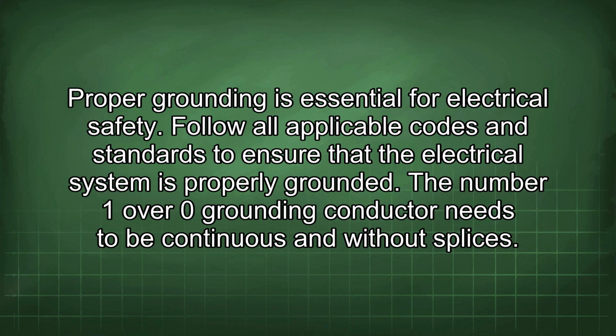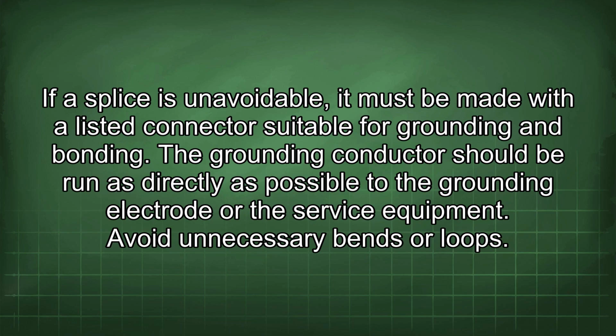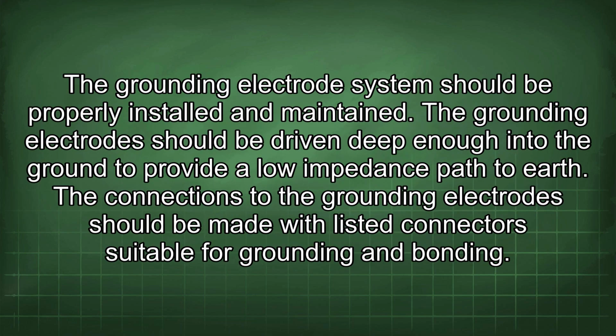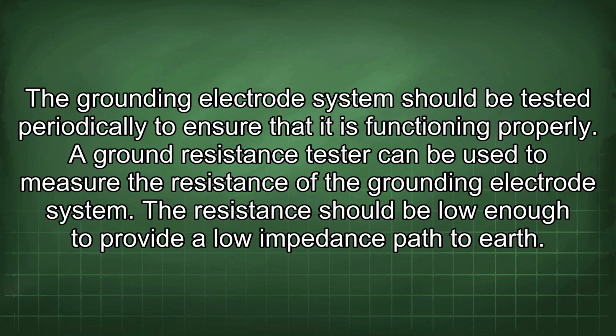The number 1/0 grounding conductor needs to be continuous and without splices. If a splice is unavoidable, it must be made with a listed connector suitable for grounding and bonding. The grounding conductor should be run as directly as possible to the grounding electrode or the service equipment. Avoid unnecessary bends or loops. The grounding electrode system should be properly installed and maintained. The grounding electrode should be driven deep enough into the ground to provide a low impedance path to earth. The connections to the grounding electrode should be made with listed connectors suitable for grounding and bonding. The grounding electrode system should be tested periodically to ensure that it is functioning properly.